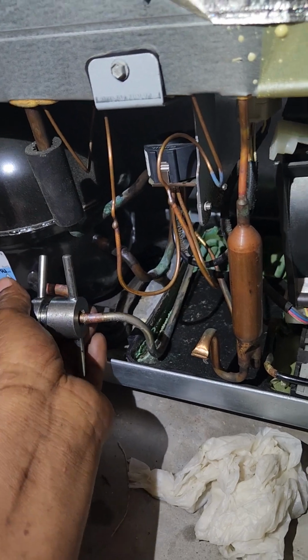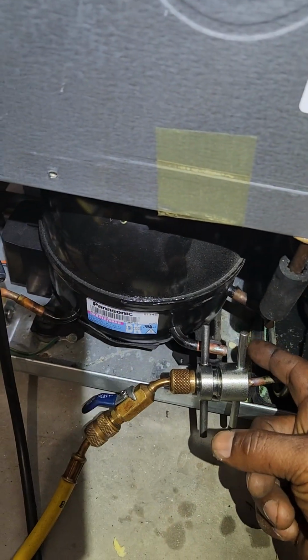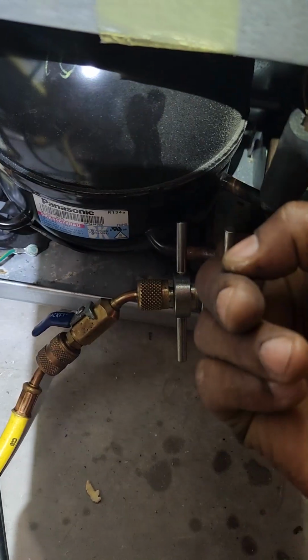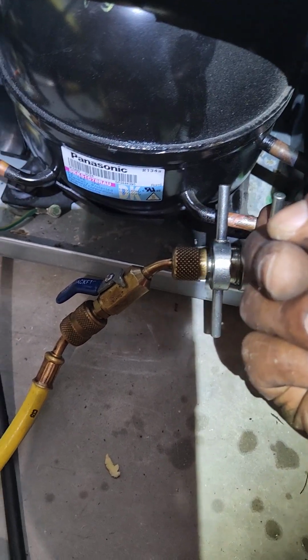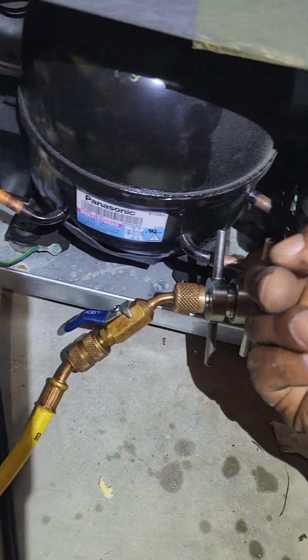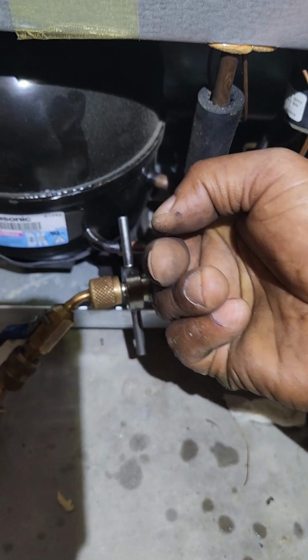home position. And another thing to point out here, now that I've got the discharge tube disconnected, the compressor is actually building up pressure. So that tells me, remember before it wasn't moving, it was just zero. I've got pressure now. It's about normal.